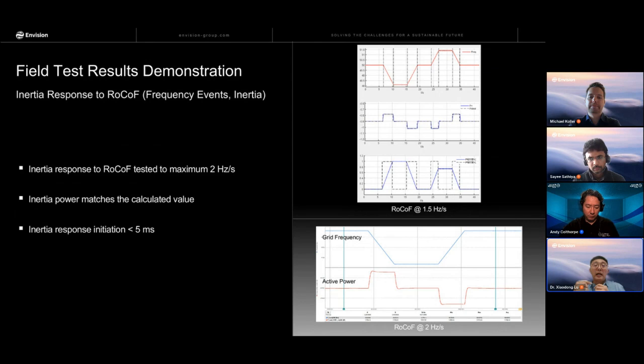We tested on site the maximum rate of change of frequency of 2 Hertz per second. You can see the result on the right side. We also have some dashed lines there to make sure the inertial power injected matches the calculated value. We also verified the inertial response time, especially the initiation time, by using the scope.